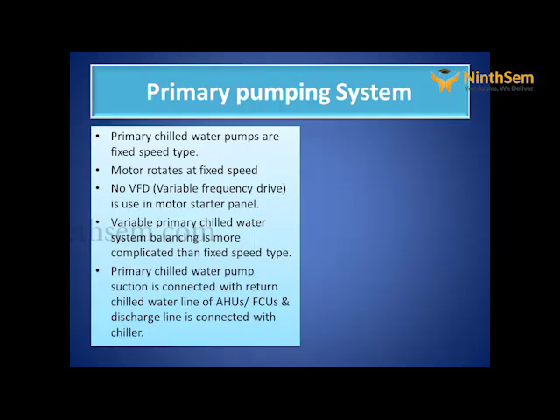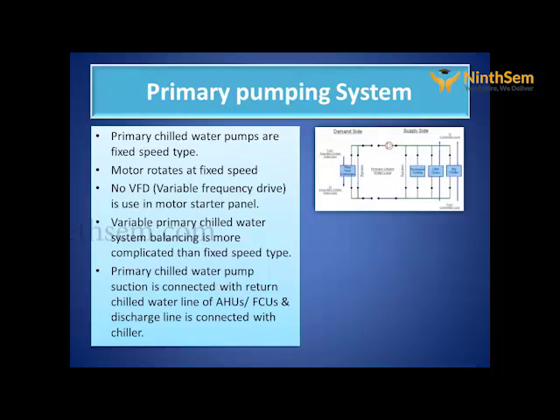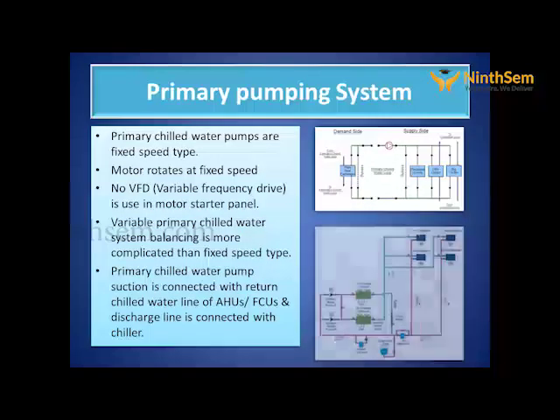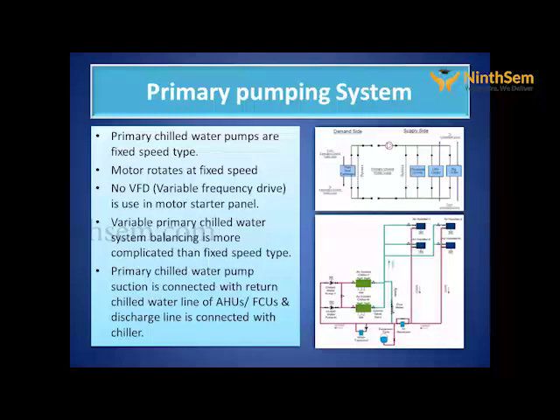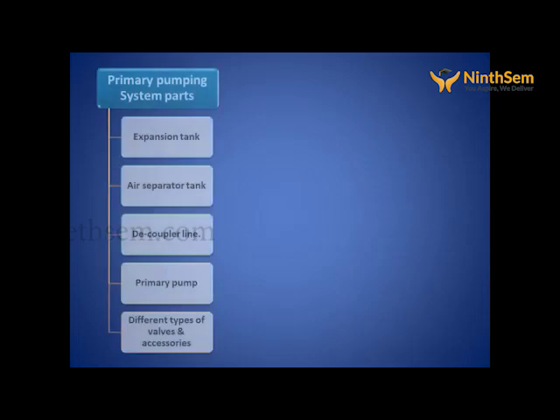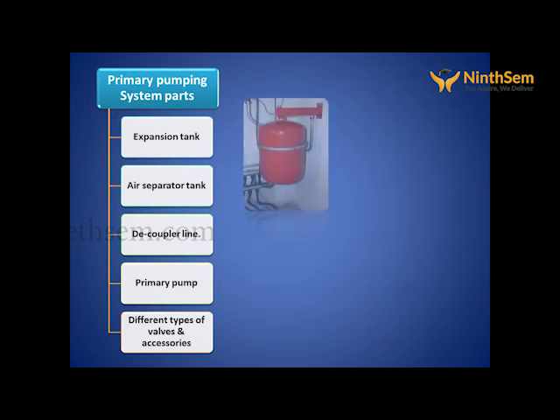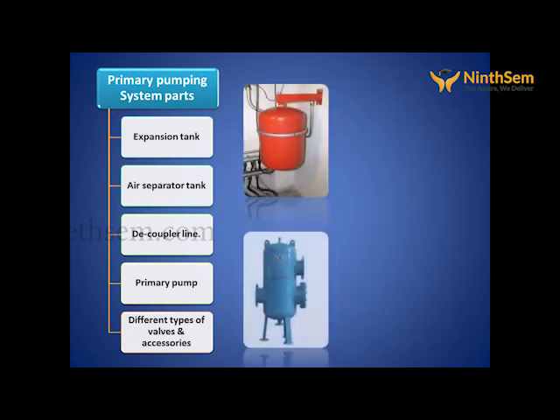Primary chill water pump suction is connected with return chill water line of AHUs, FCUs, and discharge line is connected with chiller. Now, primary pumping system. Please see the primary chill water piping layout. Here, primary chill water piping system is involved with expansion tank, air separator tank, decoupler line, primary pump, and different types of valves and accessories.